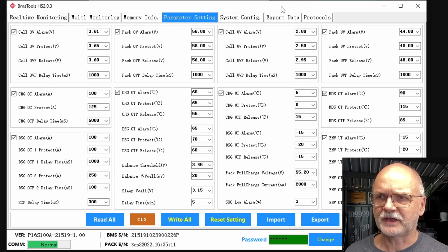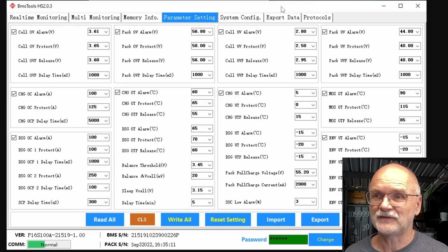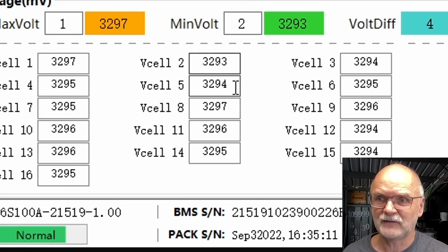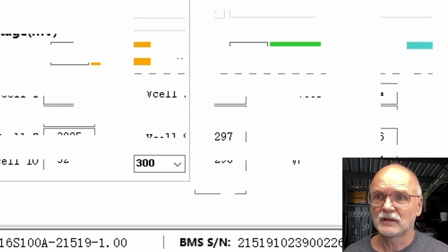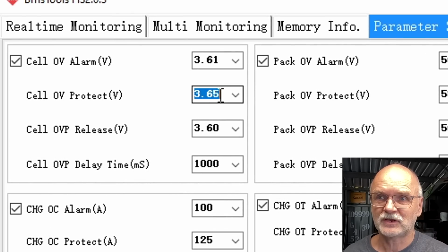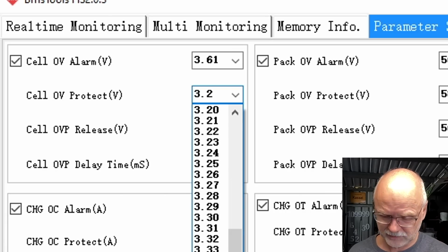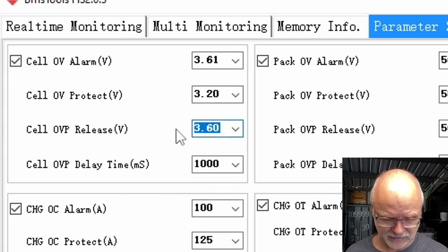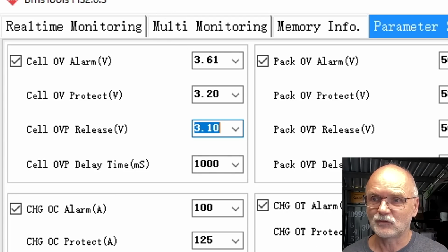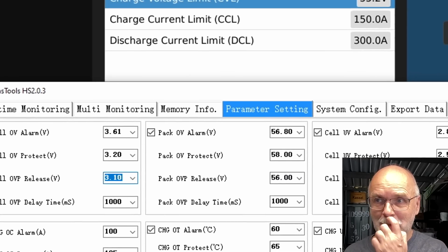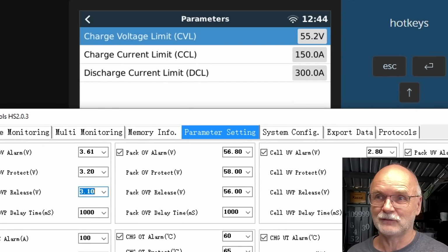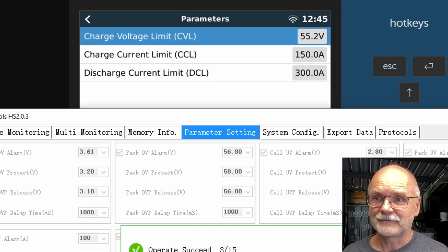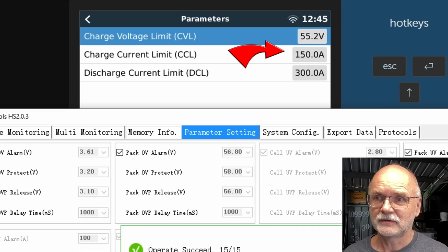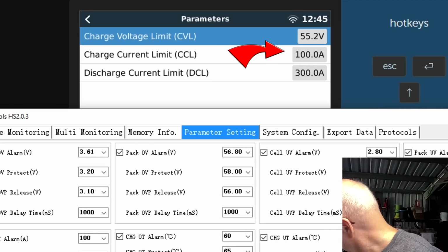okay, I just want to quickly check what happens if one of these slave batteries has an over voltage protection, for example. So for this reason, let's check what we have, 3.29 volts. And we just set the over voltage protection here to 3.2 volts. And the release needs to be lower, 3.1 volts, for example. Alarm doesn't matter. And we write this all back to the BMS. And let's have a look what the charge current limit here does when we do that. So we should get an alarm from this BMS now.